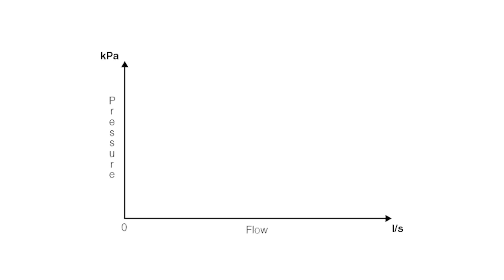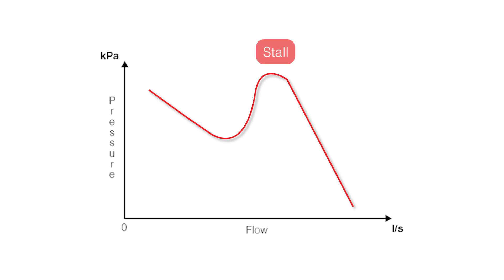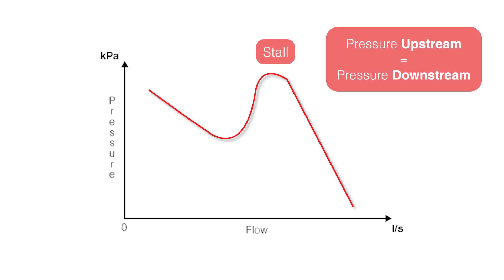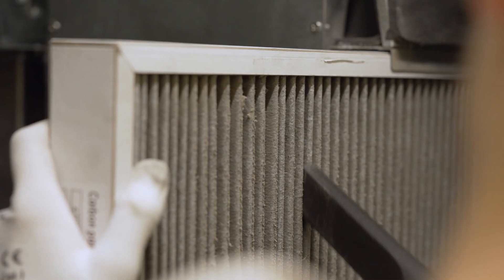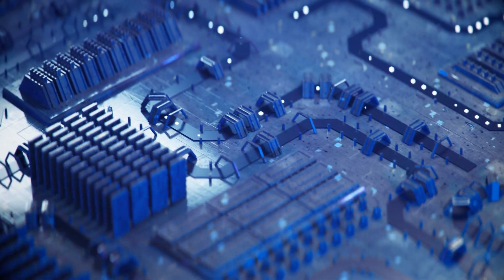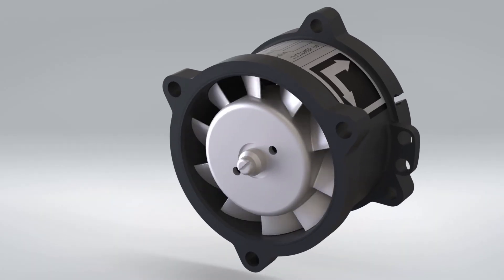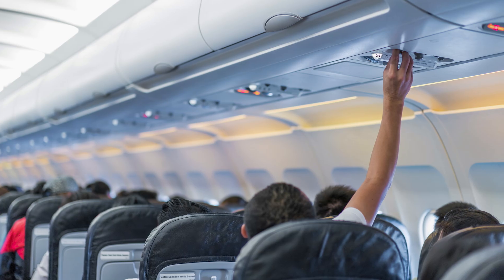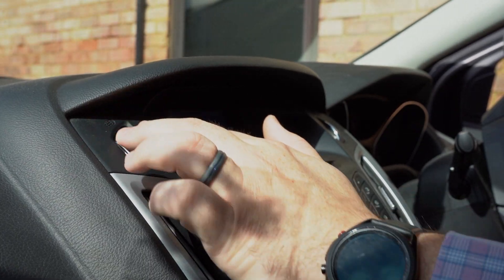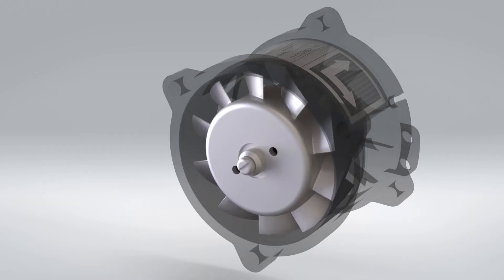However, like an aeroplane wing, a fan blade will stall and stop generating flow when it encounters certain conditions. For a fan blade, a stall condition occurs when the pressure upstream of the fan becomes equal to the pressure downstream. High pressure is generated upstream by anything resisting the airflow, including fixed grills, electronic equipment, or a variable resistance like a filter that's slowly blocking over time, or passengers opening and closing gaspers in an aeroplane or car ventilation system.